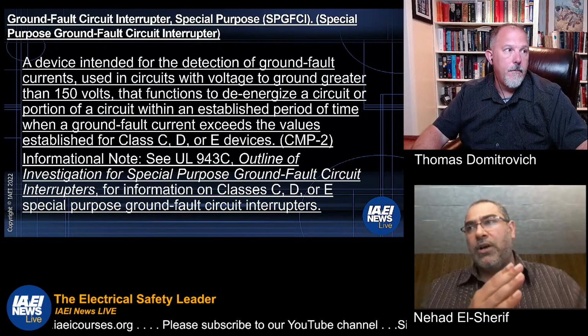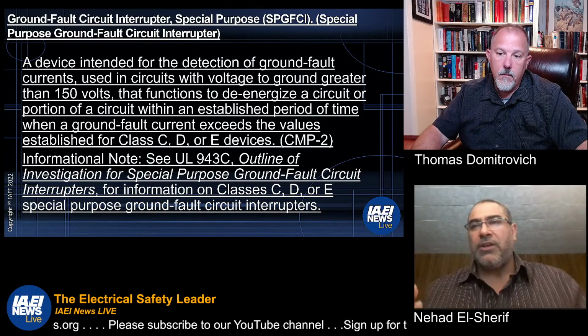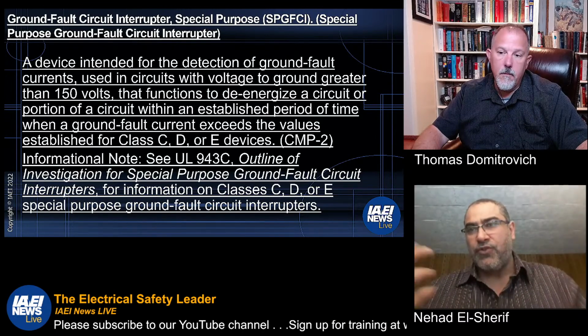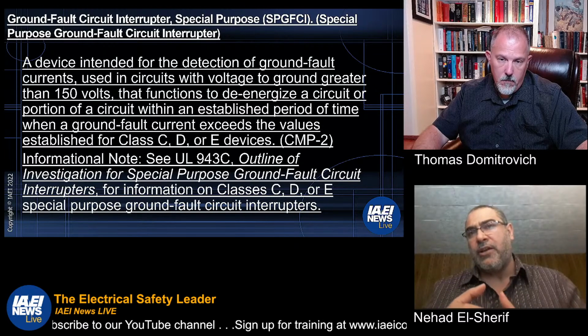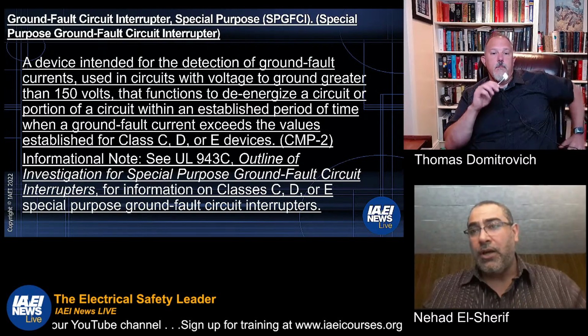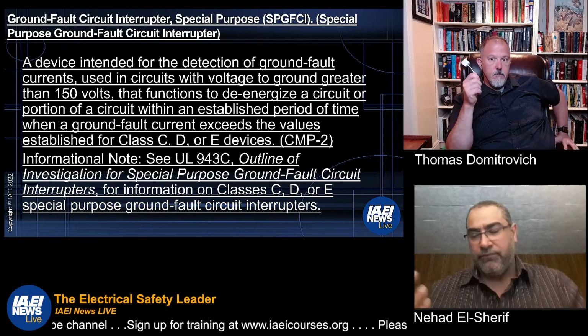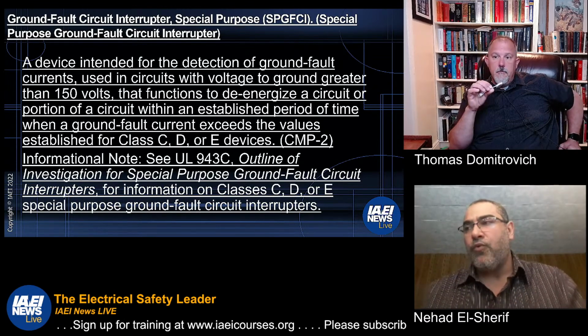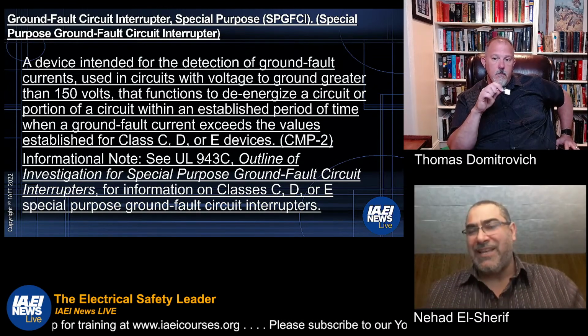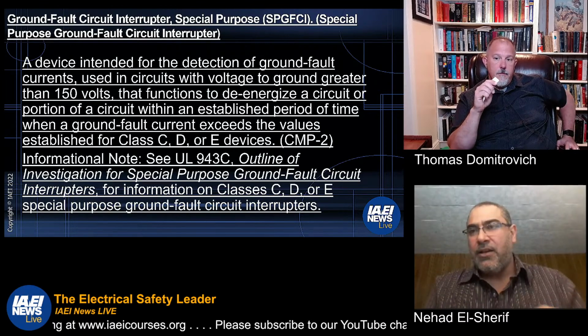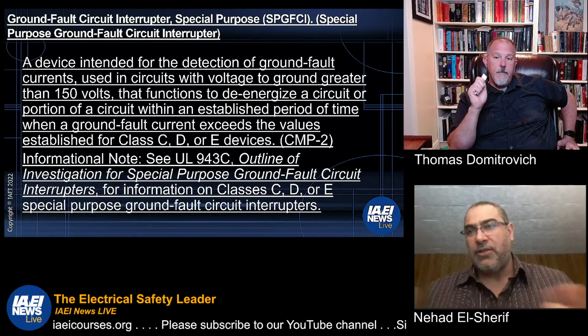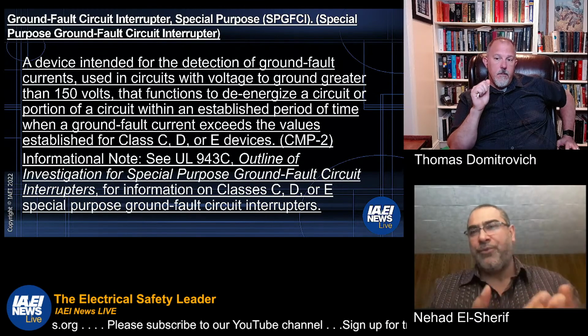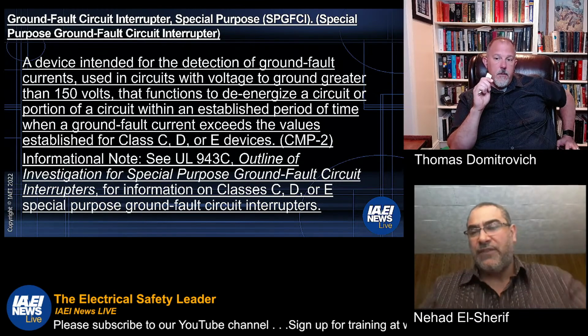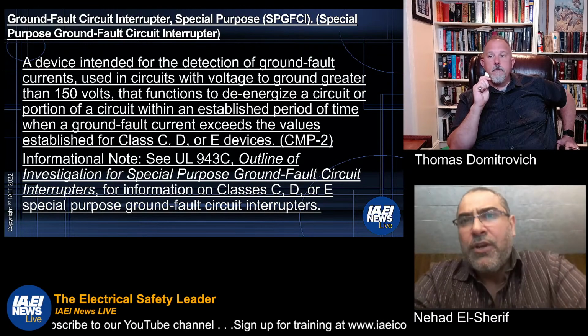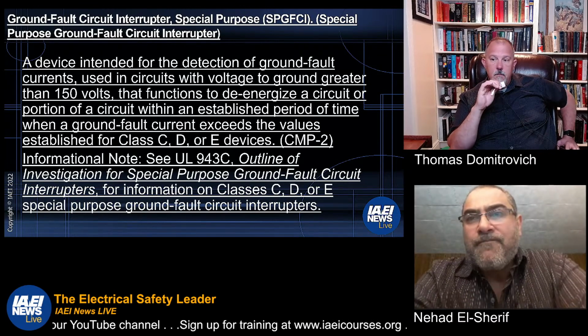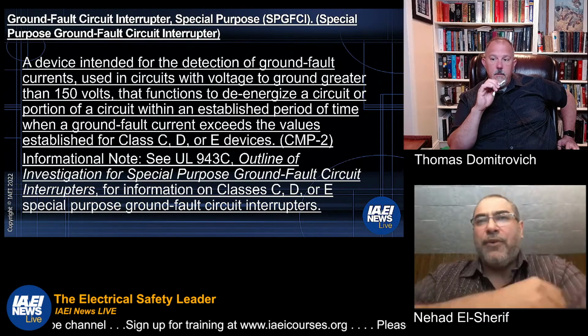This standard defined what they call Class A and non-Class A GFCIs. So non-Class A GFCIs are those GFCIs that can go up to 600 volts line-to-line voltage, which is kind of similar to Class C, D, and E, but they're not called C, D, and E in Canada. They're just non-Class A GFCIs. Anything that doesn't fit under the Class A umbrella in Canada is pretty much a non-Class A GFCI. I think that's what Merv is referring to, but please correct me if I'm wrong, Merv. But probably this is what my guess is.